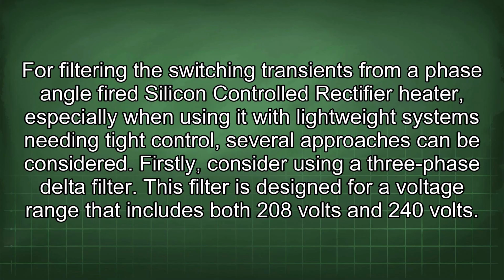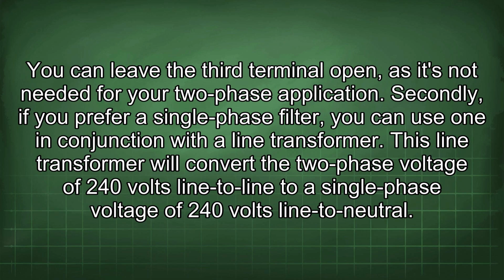For filtering the switching transients from a phase angle-fired silicon-controlled rectifier heater, especially when using it with lightweight systems needing tight control, several approaches can be considered. Firstly, consider using a three-phase delta filter. This filter is designed for a voltage range that includes both 208 volts and 240 volts. You can leave the third terminal open, as it's not needed for your two-phase application.